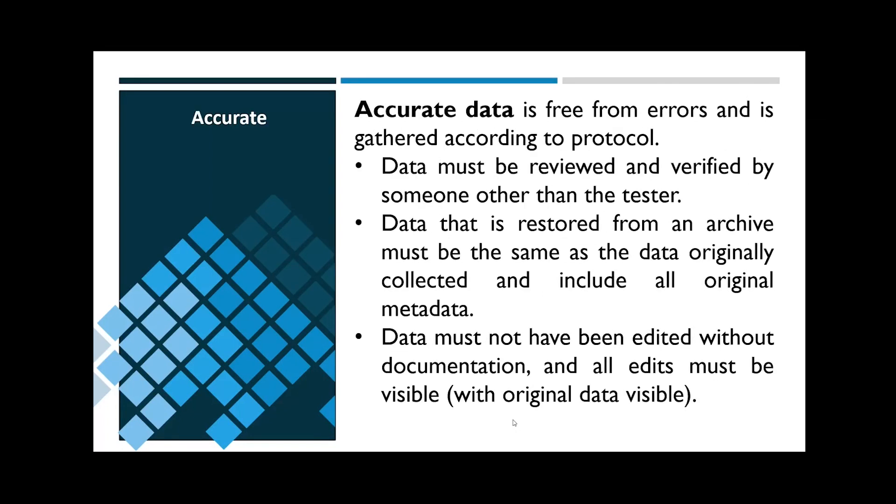Accurate data is free from errors and is gathered according to defined protocols. It must be reviewed and verified by someone other than the tester. Data that has been restored from an archive must be the same as the originally collected data and include all original metadata. Data must also have not been edited without documentation, and every edit that has been documented leaves the original entry visible.